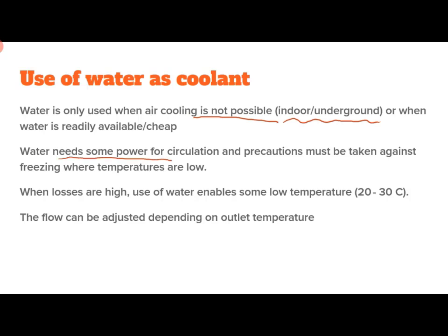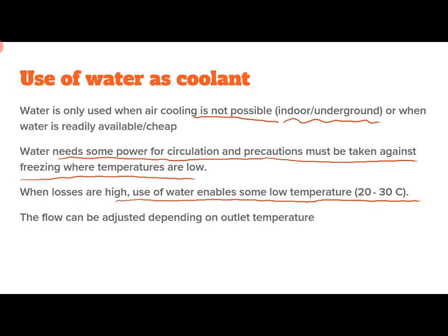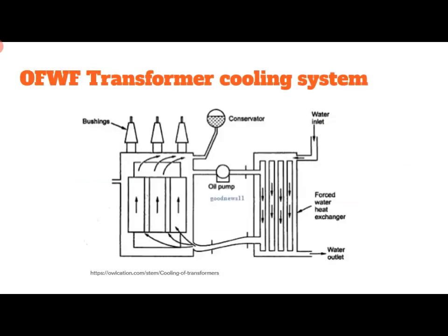The outer system will use water in some cases — for indoor or underground systems where adequate air cooling is not possible, and also where water is readily available and cheap, because the water cooling system has high efficiency. Water needs some power for circulation, and precautions must be taken against freezing in pipes where temperatures are low. When losses are high, use of water enables very low temperatures such as 20 to 30 degrees centigrade. The flow can be adjusted depending on the outlet temperature and cooling requirement.